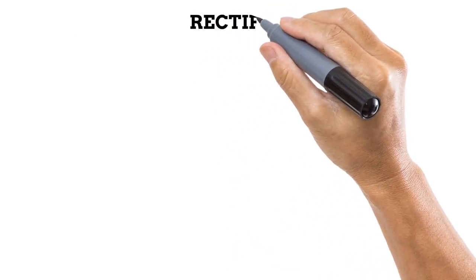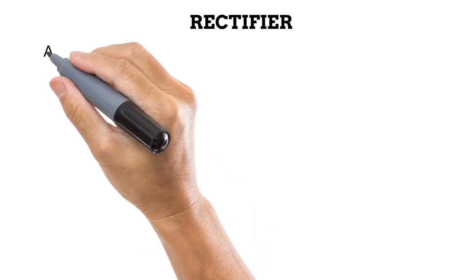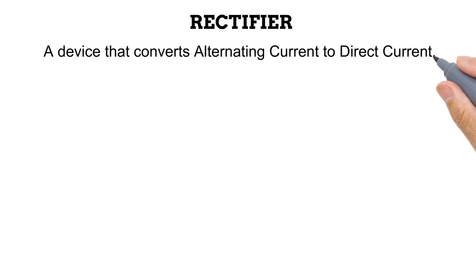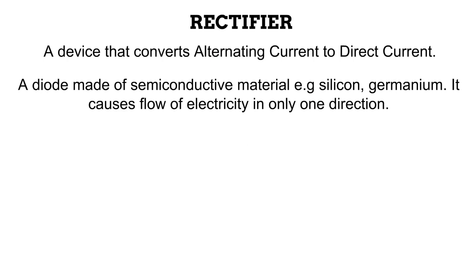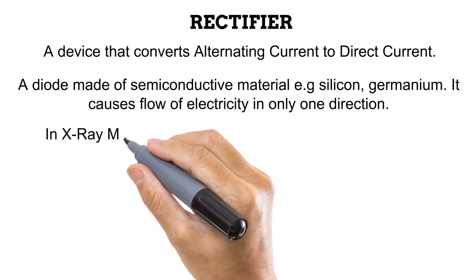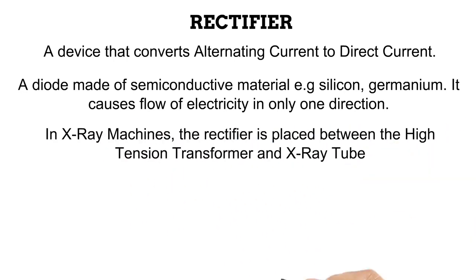As we have stated earlier, electricity flowing from the national grid is usually an alternating current. However, most devices, including X-ray tube, need direct current. A rectifier is a device that converts alternating current coming from the national grid to direct current needed by many devices. It is a diode made of a semiconductor like silicon or germanium, and it causes electricity to flow in only one direction, as direct current would. In X-ray machines, the rectifier is normally placed between the high-tension transformer and the X-ray tube.